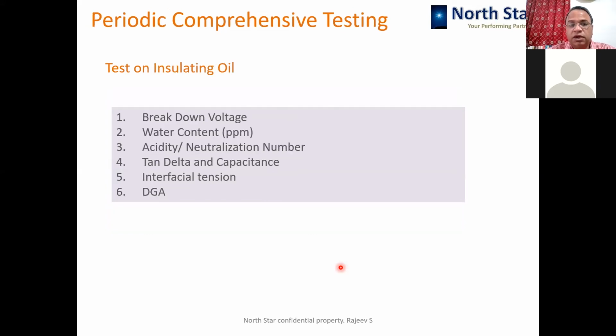When it comes to oil test, as we said, breakdown voltage, water content, and acidity. These are to be done routinely. Just do not do BDV, do water content and acidity also. Once in a while, frequency again is up to you, tan delta, capacitance, interfacial tension, and DGA. We are doing DGA not to check the oil, but basically to see the overall insulation condition in the transformer or overall condition of the transformer as such.